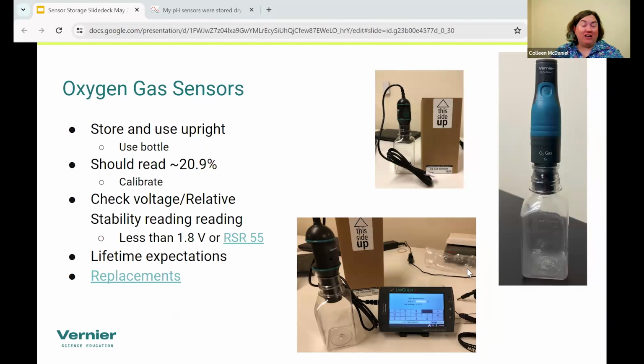And since we're talking about oxygen, let's talk oxygen gas now. Oxygen gas sensors are one of our few sensors that has very specific ways you need to store it. You absolutely need to store it upright, because there is an electrochemical cell inside of it, and if it is stored on its side, that can cause the gel inside the cell to move and give you pretty incorrect readings. So what I recommend is to store it in the bottle that it comes with, or if you keep the box, keep it in the box, making sure it's standing upright.